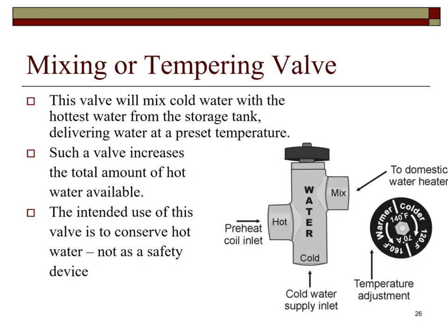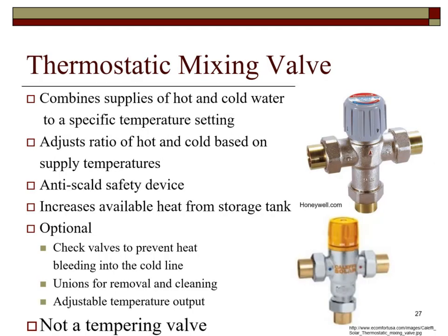The mixing or tempering valve will mix cold water with the hottest water from the storage tank, delivering water at a preset temperature. Such a valve increases the total amount of hot water available. The intended use of this valve is to conserve water, not as a safety device. A thermostatic mixing valve is a valve that blends hot water with cold water to ensure constant, safe shower and bath outlet temperatures, preventing scalding.